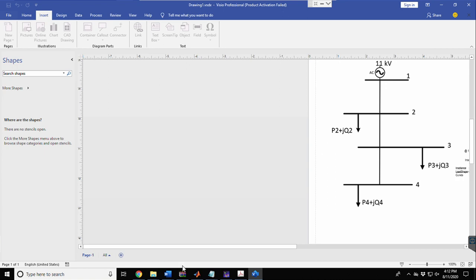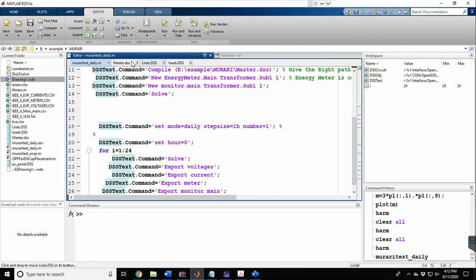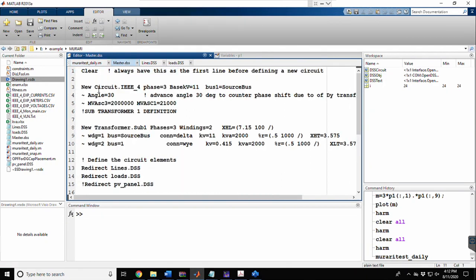Coming to the coding part, here is the master file. I have named it using the 'new' command for circuit creation, and the circuit name is IEEE_4. This circuit has three phases and the base voltage is 11 kV. The starting bus is named 'source bus'. An intentional 30-degree advance is provided to counter the phase shift due to the delta-star transformer.